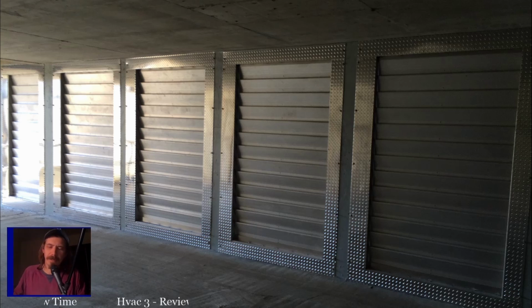But nowadays, it's a lot easier. You just have the multiple stages set up. One good way to create different stages on heat is outdoor thermostats, right? That was the old school way of making multiple stages of heat. You'd have a single stage heating thermostat, but you'd power the other stages off an outdoor thermostat. So unless the temperature dropped below a certain degree, you wouldn't kick on the extra stages of heat. We still do that a lot with hybrid systems nowadays, right?